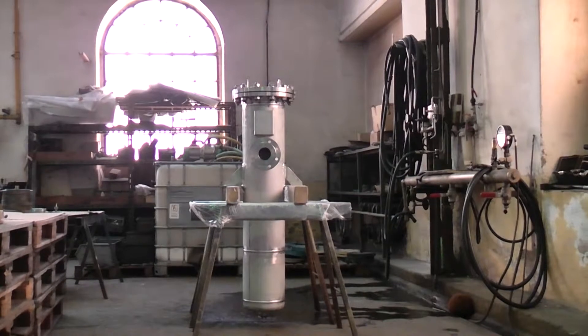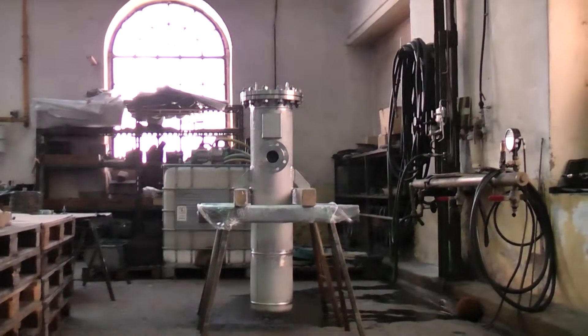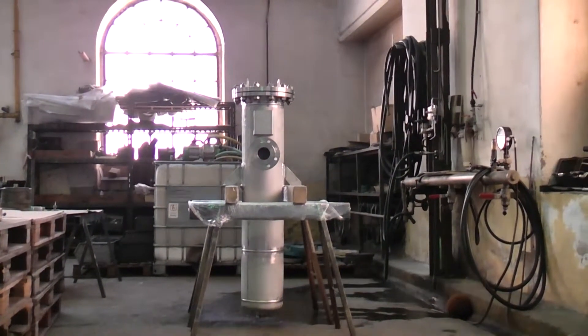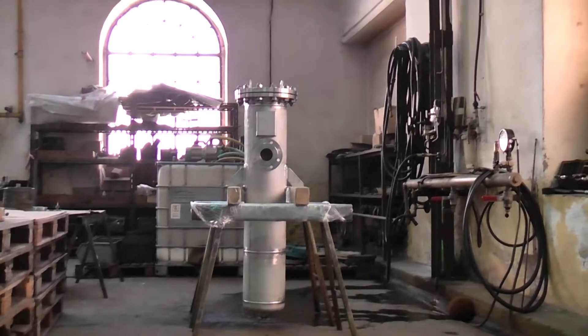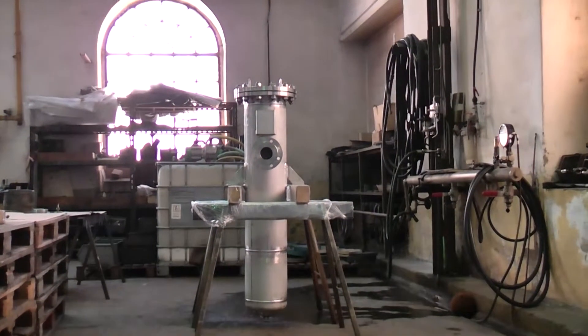The air shield is built from pleated polypropylene. It has a length of 590 mm with a diameter of 190 mm, providing an area of approximately 5.7 square meters. It has a filtration rate of 3 micron in air.